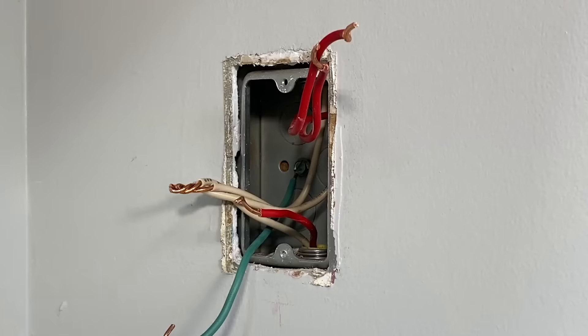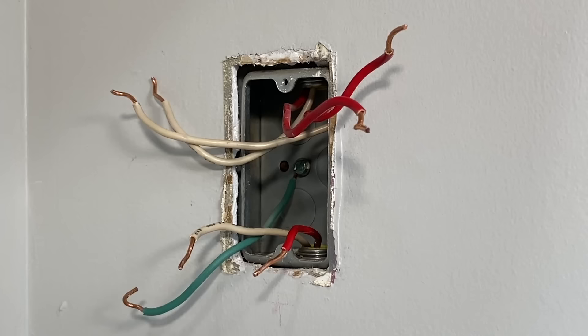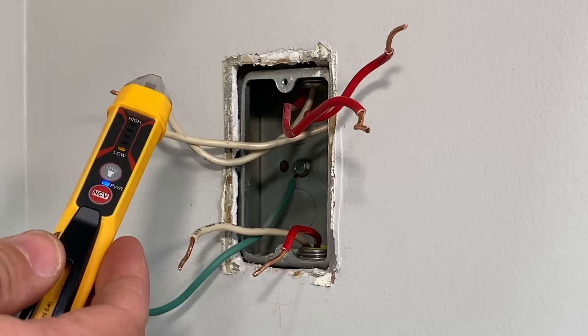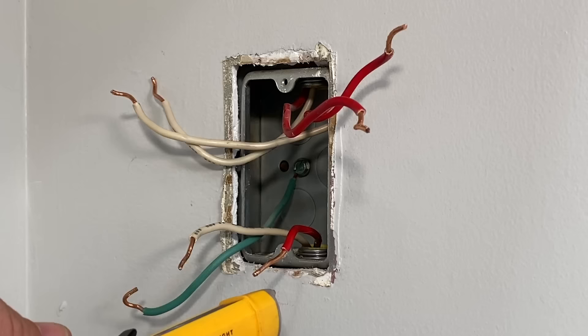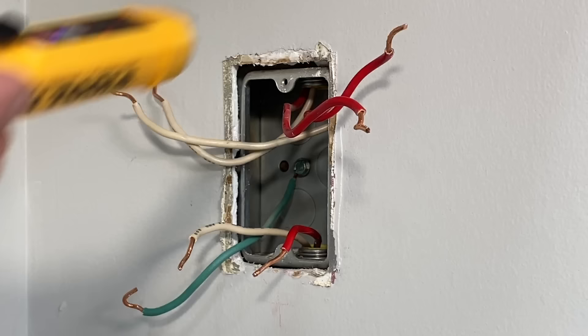The reason I'm doing that is because I want the line — the power line coming in — to go through the GFCI outlet, but also I want the two load lines to come through there. Now, to confirm which one is the line, I turn the circuit back on and carefully test to see which red wire is showing power. That will confirm which is my line. You'll see on the back of the GFCI it's labeled line and load — this one is my line.